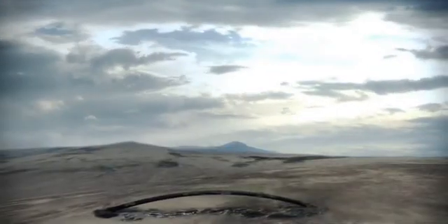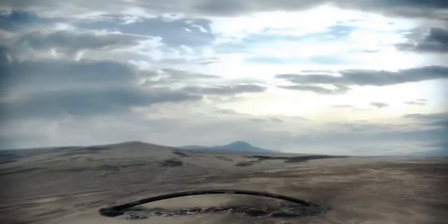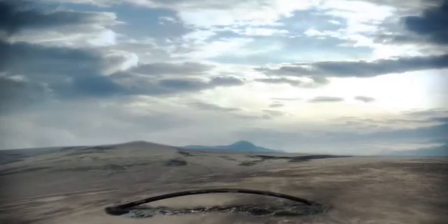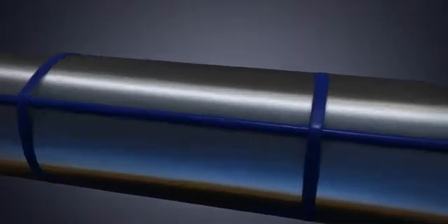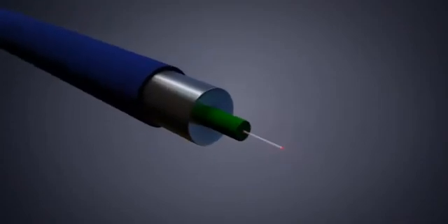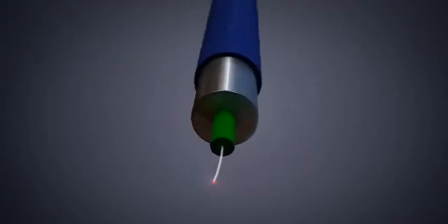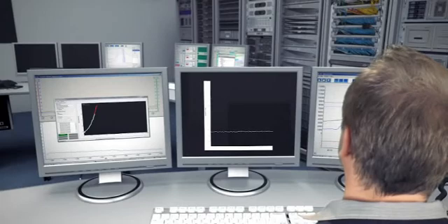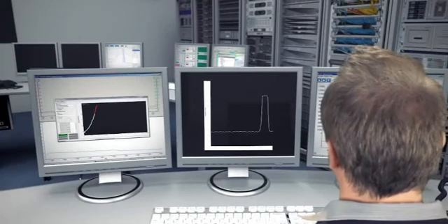In conditions where pipeline deformation is likely due to frost heave or seismic activity, fiber-optic strain sensors attached to the pipe will give early warning of upheaval or buckling development and inform the operator of the location to within one meter.